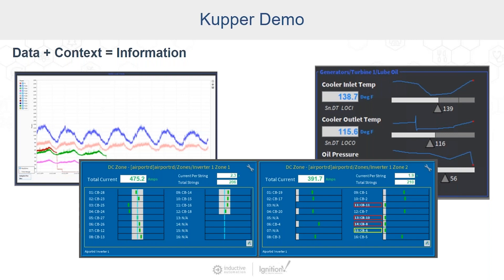These are each templates composed of other templates to minimize setup time. Finally, we have a solar combiner box monitor on the bottom, which highlights inputs that are underproducing with a circle. It visually shows the average input current against each input's value, and the acceptable deviation range is also shown as a gray band.